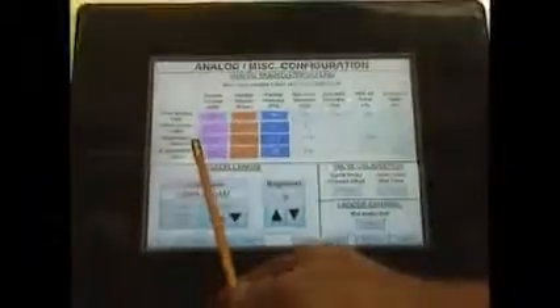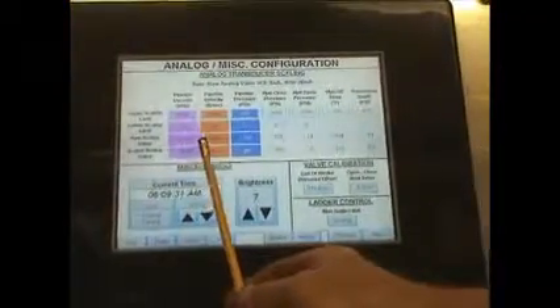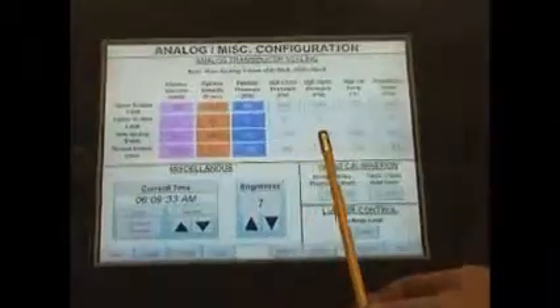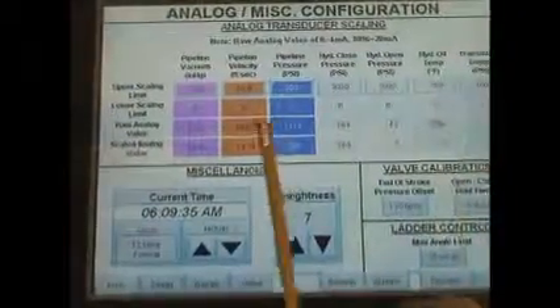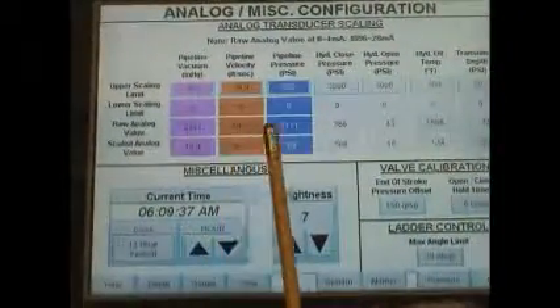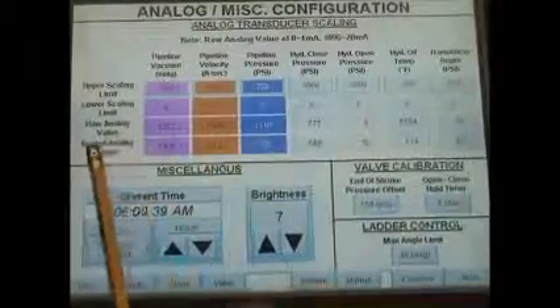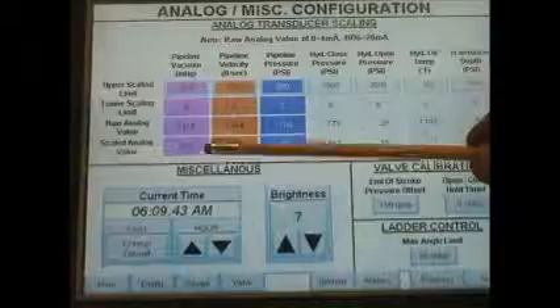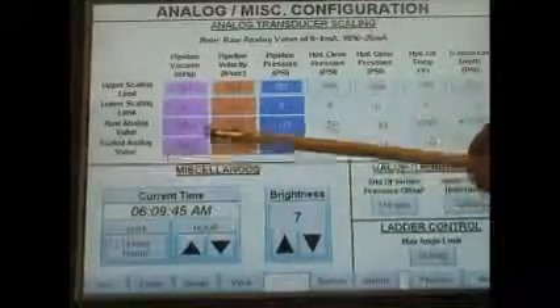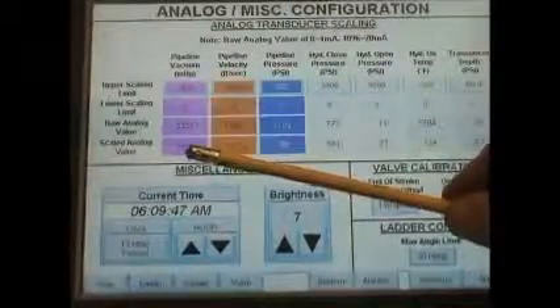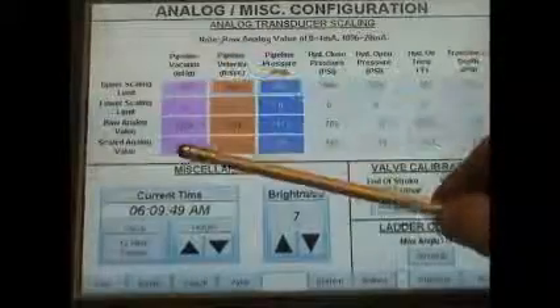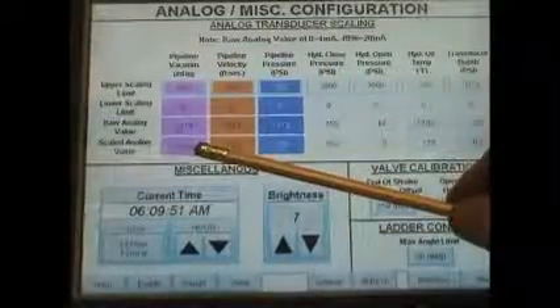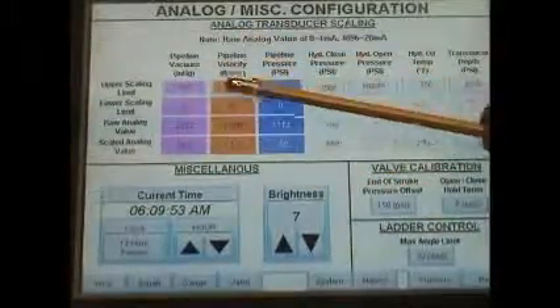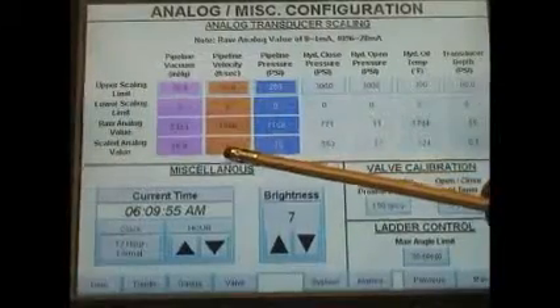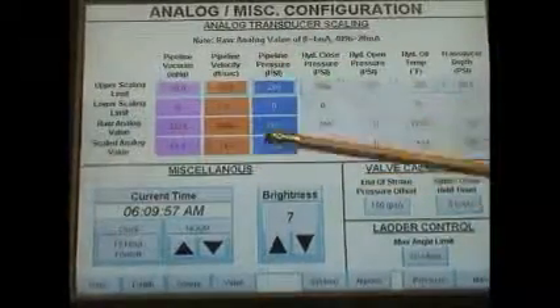The raw analog value is the value that's coming from each transducer. This tells us what our raw data is. Our scaled analog value is the actual reading of the transducer that you see on your main screen. So for example, right now our main screen on the vacuum is 16.9 inches of mercury. Our pipeline velocity is currently at 14.3, and so on.